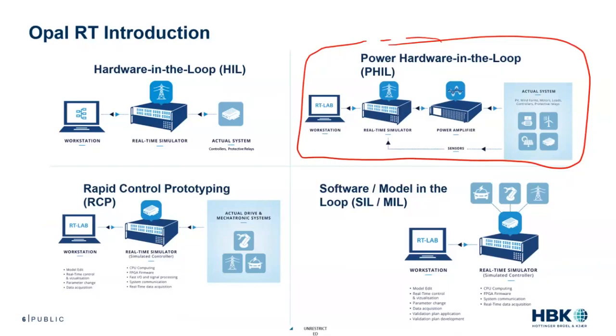So how do we work this out? You still have a real-time simulator simulating the environment, and you still have an actual controller that's going to be connected to your system. But in between, you have a power amplifier, which helps amplify the signals being simulated in your real-time simulator and feed that controller or inverter with real current. And we take the feedback via sensors, current transducers, voltage measurements back into the real-time simulator, which helps us see how your controller or your inverter or whatever device is being tested is behaving.